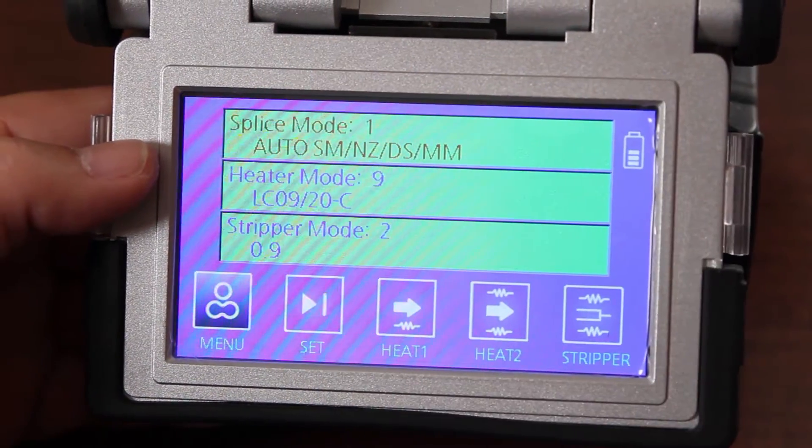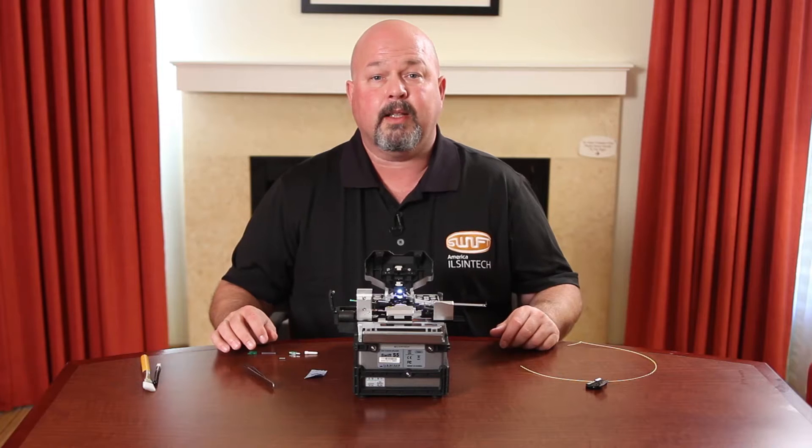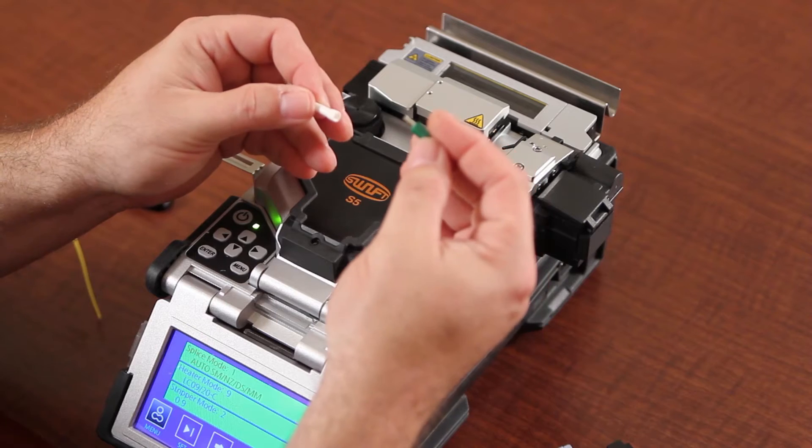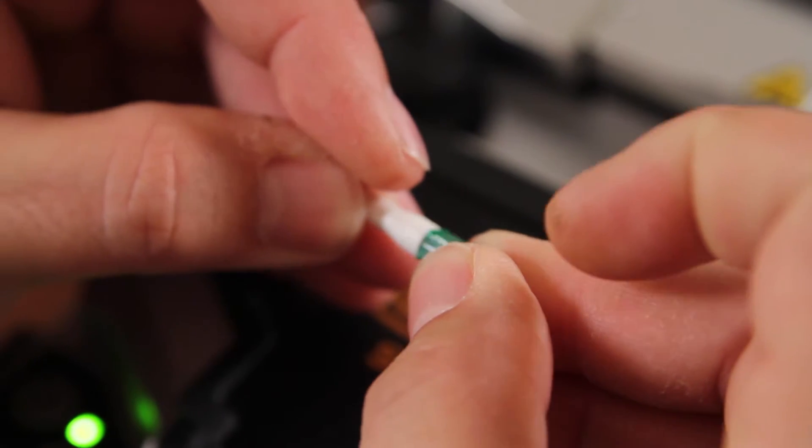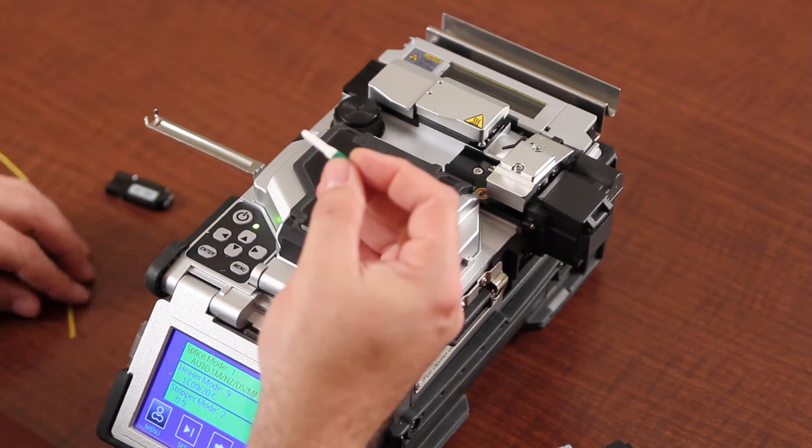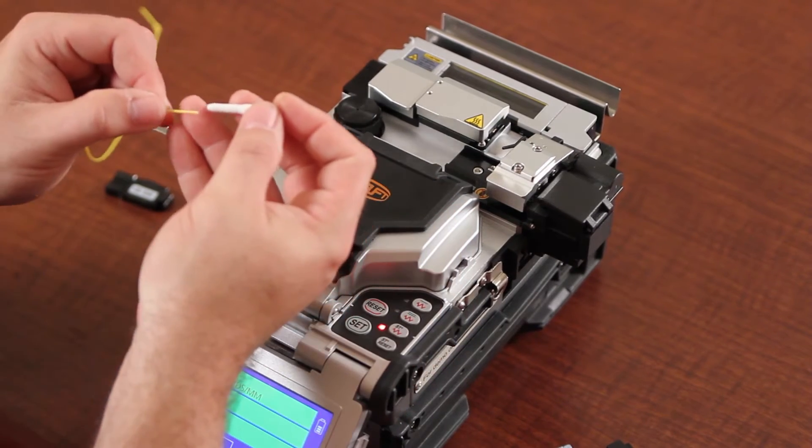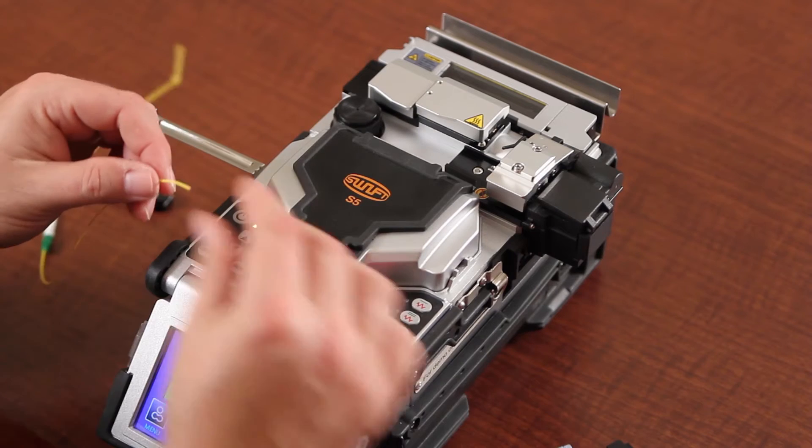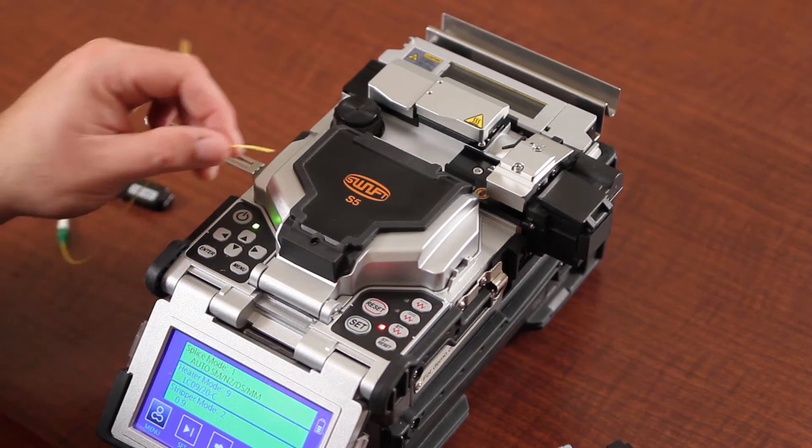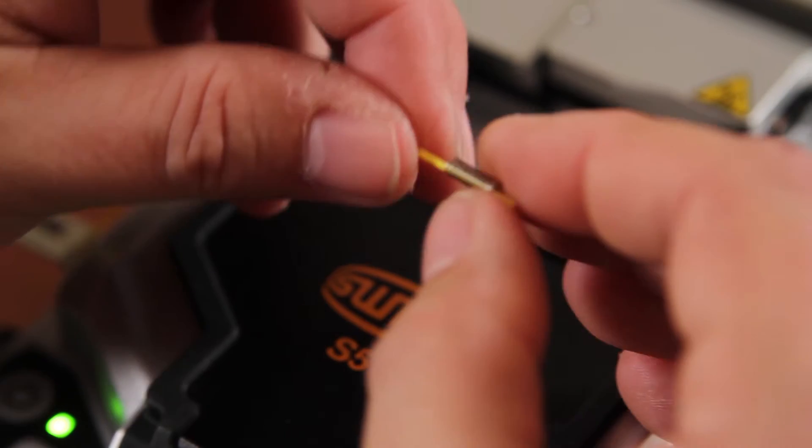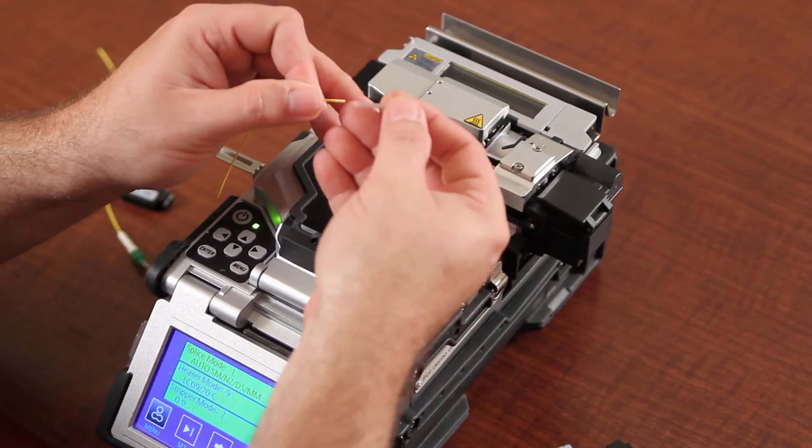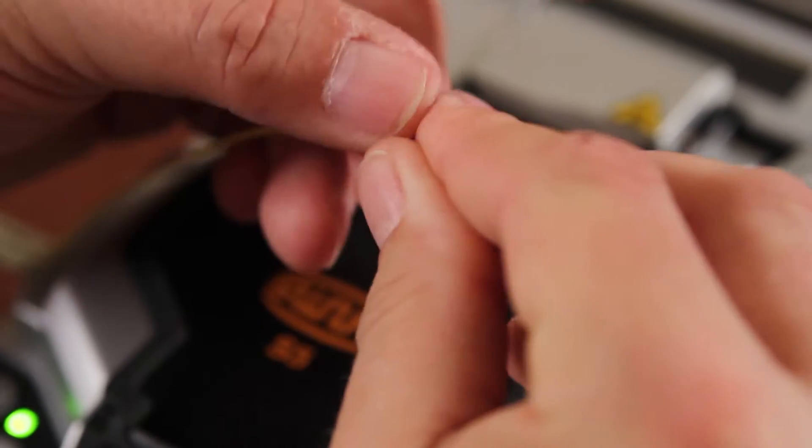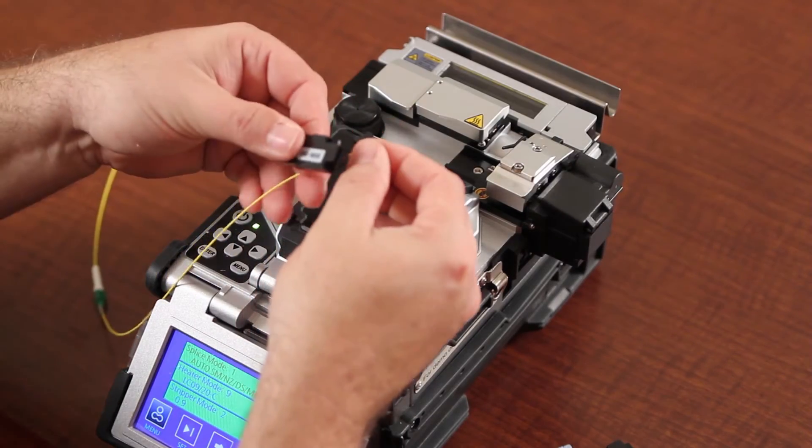Make sure your stripper is set to 900 micron. At this point, prep your left side. First, take your back boot and install it onto your back shell and install onto your fiber. Place your spring and your heat shrink. Install into your holder.